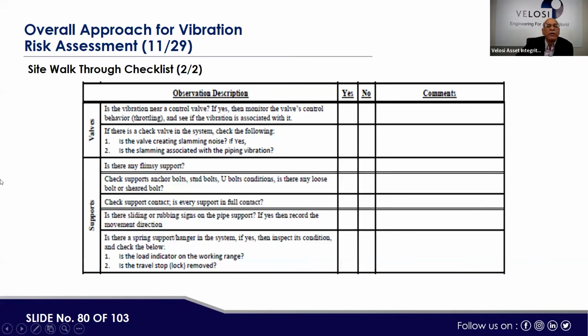Then, is the vibration due to a control valve? If yes, then monitor the valve control behavior like throttling and see if the vibration is associated with it. If there is a check valve in the system, check the following: is the valve creating a slamming noise? If yes, is the slamming associated with the piping vibration? Is there any flimsy support, like check support, anchor bolt, stud bolt, U-bolt condition? Is there any loose bolt, sheared bolt? Then check support contact: is every support in full contact? Is there any sliding or rubbing sign on the piping support?